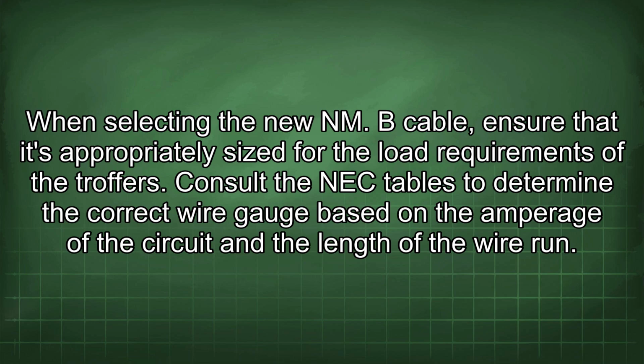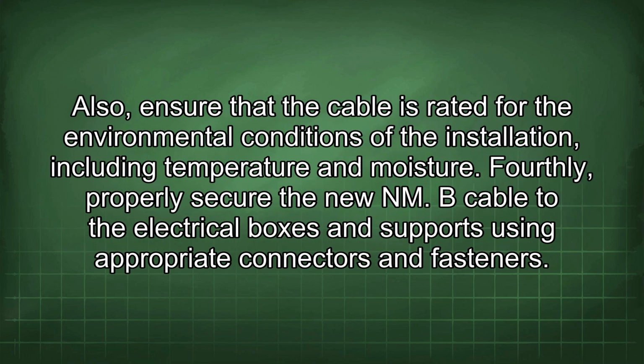of the wire run. Also, ensure that the cable is rated for the environmental conditions of the installation, including temperature and moisture. Fourthly, properly secure the new NM-B cable to the electrical boxes and supports using appropriate connectors and fasteners.